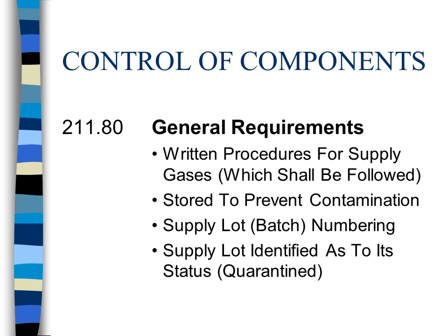We have written procedures for your supply gas, your D55, or your analytical gases to calibrate your Servomex. The supply lot and batch numbering system, the lot number, for example, is your total history of the manufacture of that product.